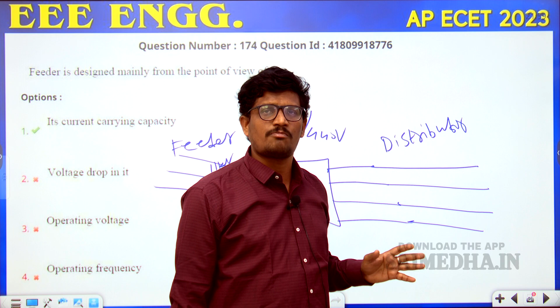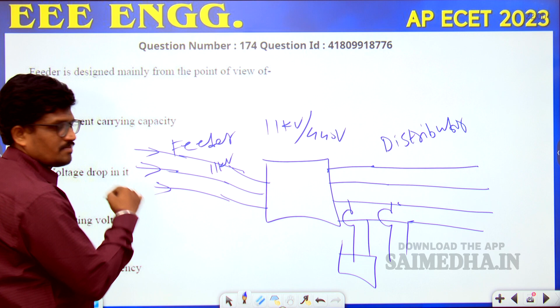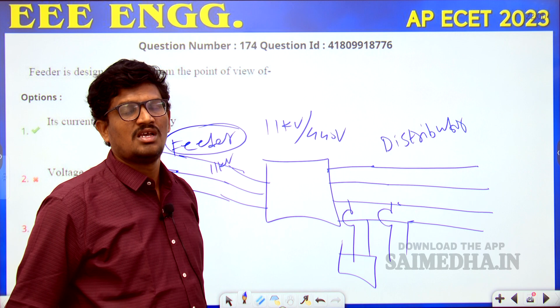A line without any tappings is called a feeder. There are no tappings in a feeder because it is a primary distribution line, so consumers do not draw power from it directly. That's why the flow of current is the same throughout the feeder. That is the reason the feeder design depends upon the flow of current, while the distributor design depends upon voltage drop.